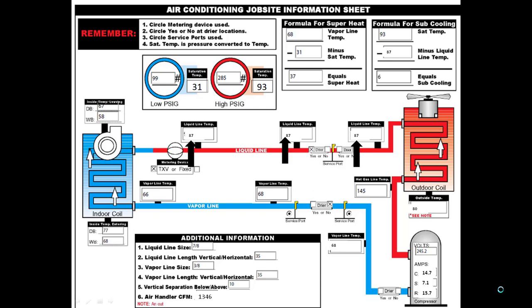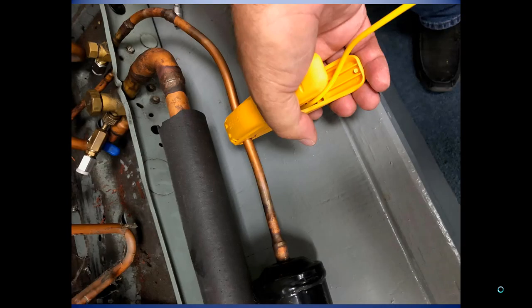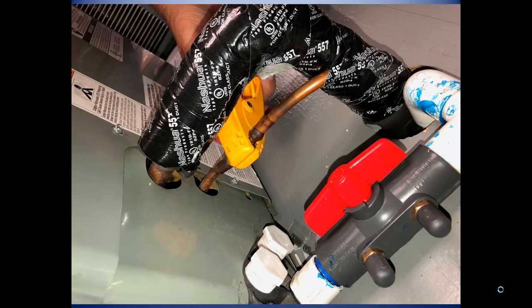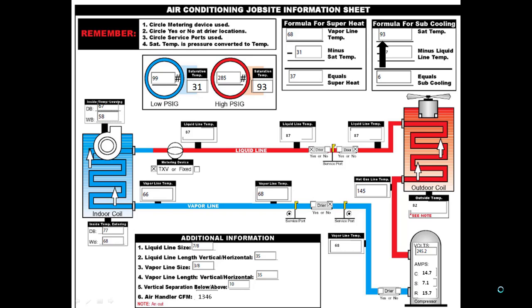Move on to the liquid line temperature. We want to take that in 3 places here: before the dryer, after the dryer, and at the air handler. We'll place those numbers here on the job site information sheet. And by doing so, we'll take these readings and convert them into subcool. Same thing with the suction line readings. We'll take the vapor line temperature and saturation temperature and convert that into superheat.